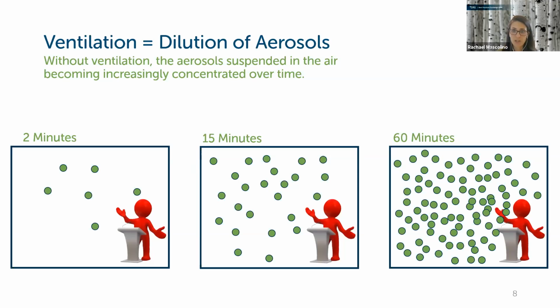So we want to make sure that we have the necessary ventilation in place based on the activity that's going on in this space and the number of people and the area of that space. Obviously, it's going to be different if you have one person speaking or you have an auditorium where there's 400 people. These are all things that we want to assess in your specific building, and even within zones of your specific building. So if I think of a school, a classroom is going to be different than maybe a cafeteria, where the ventilation varies between 0 or 100 occupants, versus a classroom where it's a pretty steady occupancy throughout the day.